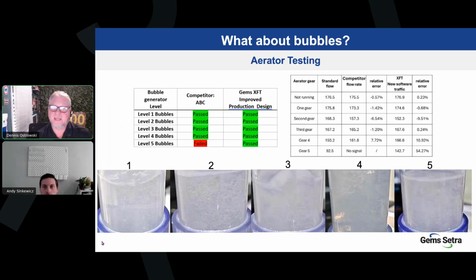Okay, another round of testing that was required was for bubbles. In many applications, it's not uncommon that there will be bubbles, cavitation, foam even. All of that is going to affect the flow rate, right? Because if you have cavitation, or air bubbles, or foam, that's going to change the sound velocity, the time of flight for the ultrasonic sound waves. So, with that being affected, we did extensive testing. We also did it against a competitor. Competitor is not ABC. We just left the name out to protect the innocent.